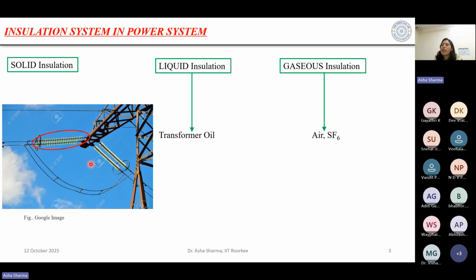When we talk about liquid insulation, a very common example is transformer oil. This transformer oil serves two purposes: it is used for cooling as well as for insulation. When it is used for insulation, the quality of the oil must be good enough. The reason is that in a transformer we have windings, and the windings produce very high losses. The transformer oil must be able to sustain those high losses. The third one is solid insulation. Solid insulation is most commonly used, and in most cases we use this type instead of liquid and gaseous insulation.